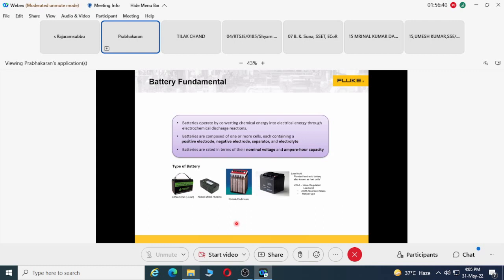Today you may be using more sealed batteries. In such conditions, you may have to use digital battery analyzers, which help you find the underlying conditions, electrolyte conditions, or heat conditions of the batteries in your facilities. Even though they're called sealed maintenance-free batteries, there is no such thing as a truly maintenance-free battery. If you are not maintaining it, it will fail, and you will end up with failures and downtime in your systems.